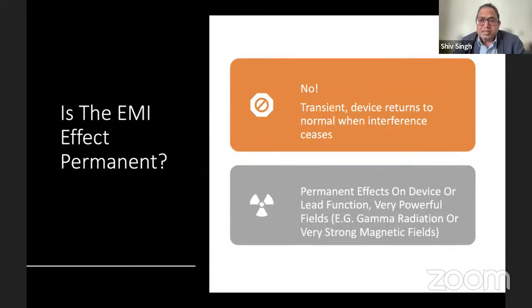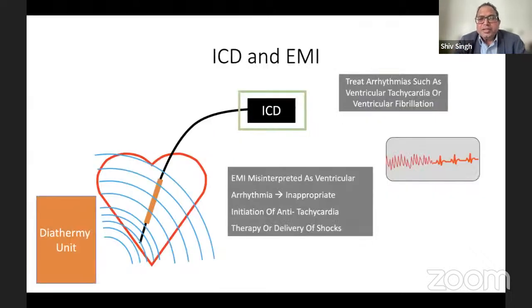So is the EMI effect permanent? No, it's not. It's transient. The device will go back to normal when the interference ceases. Okay. But a permanent effect can occur in situations where there is a very strong, very powerful field like gamma radiation, or a very strong magnetic field like MRI. We wouldn't want to take a patient with an ICD to that. So the ICD, as we said, is used for treating ventricular tachycardia and ventricular fibrillation, and EMI can be misinterpreted as ventricular arrhythmias and lead to inappropriate shocking and activation of the antitachycardia function. So diathermy machines are dangerous for ICDs, and that's why ICDs need to be deactivated before the patient is taken to theatre.